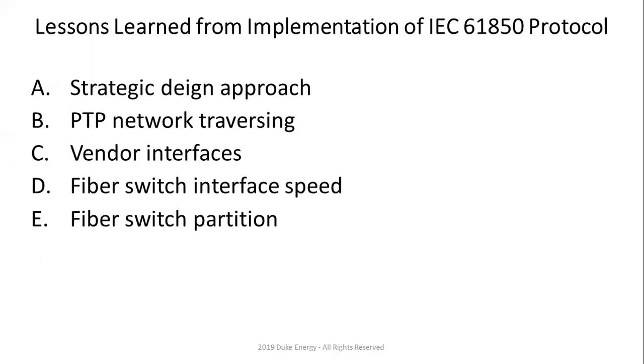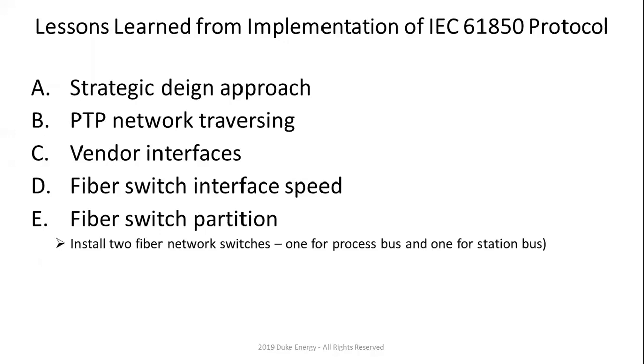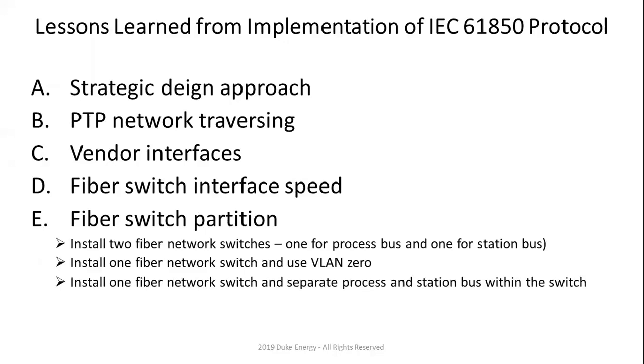That's called fiber switch partition, right? So we had the option to install 2 fiber network switches, one for process bus, one for station bus, again, either sample values or GOOSE messages, or we could do one fiber network switch and have everything come into it, so we have VLAN 0, but this is not according to the standard. Or we had one where we can do one fiber switch and we can separate process bus and station bus, which is what we did, right?